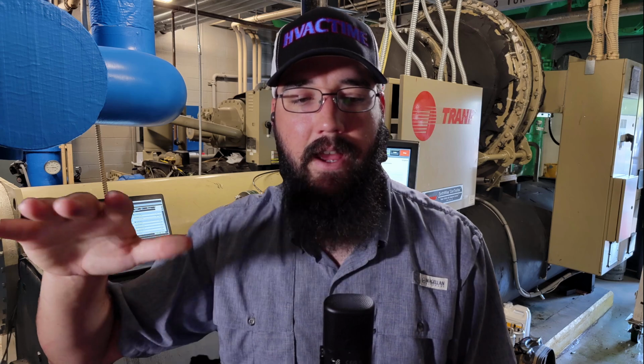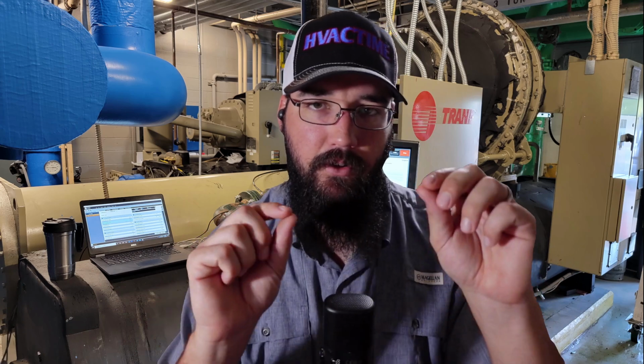So that just comes back to the person. I personally appreciate a live feed, but you have to be careful with live feed because it can be more deceiving. At the same time, having that consistency in the reading can make it easier to read and interpret, and we don't see so much fluctuation. And that's kind of the whole purpose of that smoothing, is there's not as much fluctuation to the reading, and it's meant to be more consistent and averaged. So just making you aware of that.